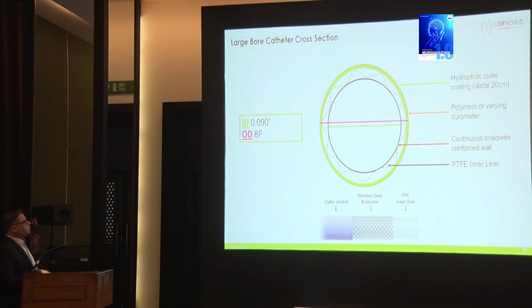This is how the cross section of the Cerebase looks like. There's an outer hydrophilic coating on the distal 20 centimeter. Then a polymer of varying durometer. This is very important because this durometer provides softness where it's required on the distal portion, and stability on the proximal portion. There's a braid running all across the body of the catheter, and then an inner PTFE lining. This is a stainless steel braid wire, from the tip to the hub of the catheter.